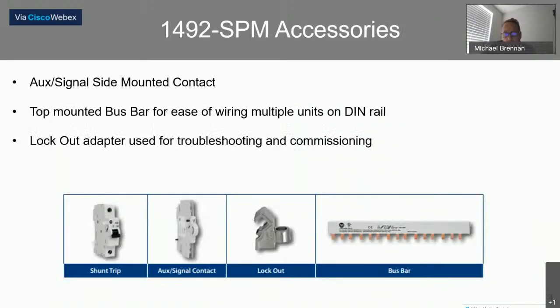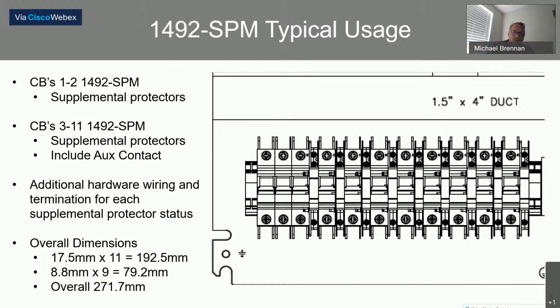Some of the nice things about the 1492 SPM are the accessories that are available for it today. Additionally, there is an aux contact available, so you can get trip status or on-off status back to a PLC specifically for that branch or that supplemental circuit. There's a shunt trip available, so if you wanted to remote trip that specific circuit, you could do that. And additionally, there's a lockout device available. For simplification of wiring, there's a bus bar that can be used along the top of the supplemental protectors. What that would allow you to do is just run larger gauge wire and feed a bunch of different supplemental circuits. So here's an example of 11 different circuits utilizing an application.